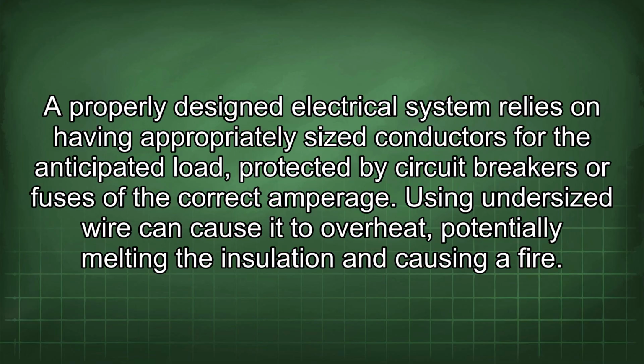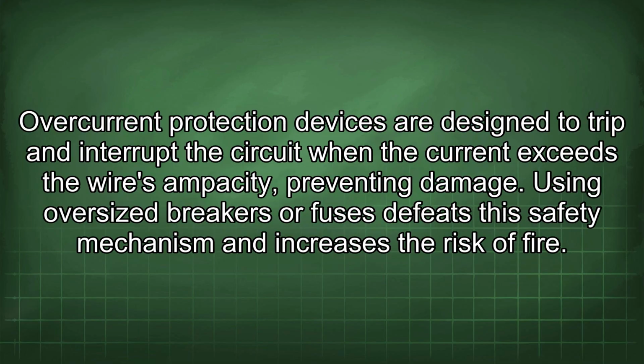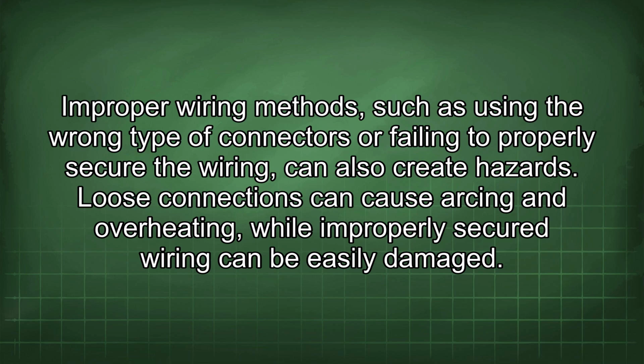Using undersized wire can cause it to overheat, potentially melting the insulation and causing a fire. Overcurrent protection devices are designed to trip and interrupt the circuit when the current exceeds the wire's ampacity, preventing damage. Using oversized breakers or fuses defeats this safety mechanism and increases the risk of fire. Improper wiring methods, such as using the wrong type of connectors or failing to properly secure the wiring, can also create hazards. Loose connections can cause arcing and overheating, while improperly secured wiring can be easily damaged.